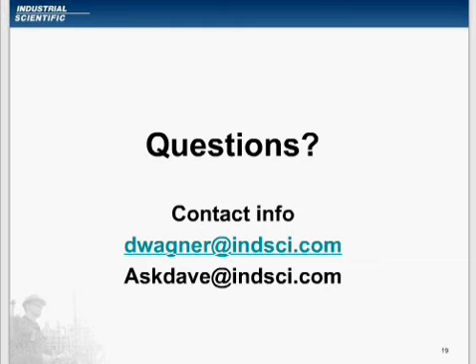Well, we still recommend a daily bump test in general. We've relaxed our recommendations to some degree with DualSense technology, and we're recommending that an instrument with DualSense technology be calibrated every 30 days, recognizing that you are much safer with 2 sensors, and to some degree you can forego bump testing, but certainly you are always safer, and you will continue to be safer if you bump test before each use.